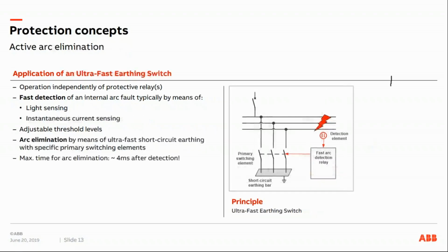As a third option, we have active arc elimination, such as the UFES. Here we have a primary switching element, as you can see here. We have a fast arc detection relay. And what's happening here, we have a fast detection of an internal arc fault by means of light sensing and instantaneous current sensing. The arc elimination itself is done by means of ultra-fast short circuit earthing with specific primary switching elements, which are here. So here you have the fault detection and then the signal triggering, leading the primary switching elements to eliminate the arc. Here we are typically talking about an arc elimination time of 4 milliseconds after detection.